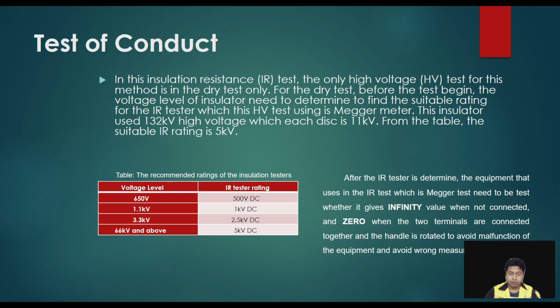Okay, for the test conduct, in this insulation resistance IR test, the only high voltage HV test is for this method, which is the dry test only. For the dry test, before the test begins, the voltage level of the insulator needs to be determined to find the suitable rating for the IR tester, which is the HV test, using the Megger meter. So this insulator uses 132 kV high voltage, which each disc is 11 kV. From the table, the suitable IR rating is 5 kV.